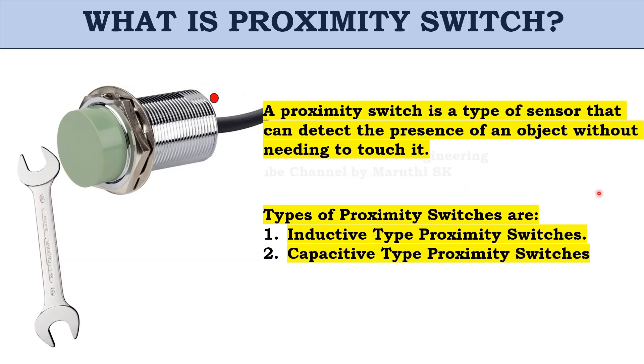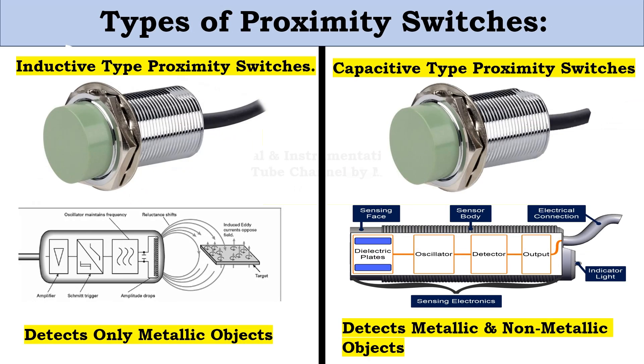Types of Proximity Switches: there are two types present in the market — Inductive Type and Capacitive Type. Both look the same in physical appearance, but the internal working principle is different. The Inductive Proximity Switch detects only metallic objects, while the Capacitive Proximity Switch detects both metallic and non-metallic objects.